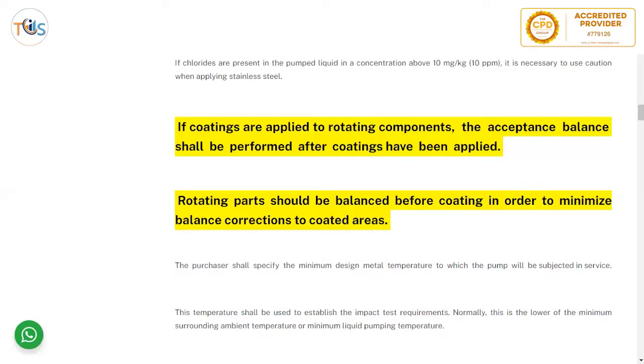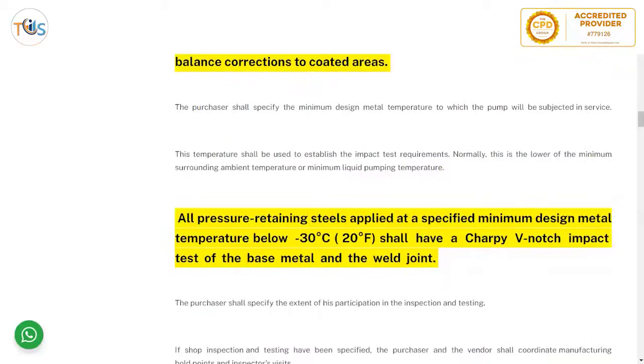The purchaser shall specify the minimum design metal temperature to which the pump will be subjected in service; this is the purchaser's responsibility. This temperature shall be used to establish impact test requirements and is normally the lower of the minimum surrounding ambient temperature or the minimum liquid pumping temperature. Based on ambient temperature — the lowest mean in the last 10 years plus 8 degrees Celsius — that gives the design metal or liquid temperature.